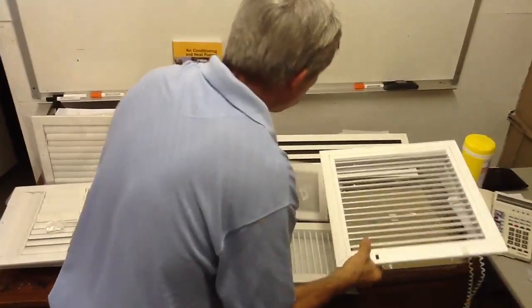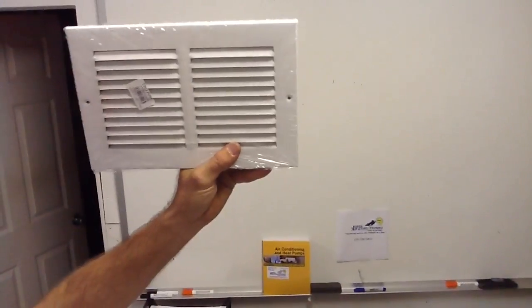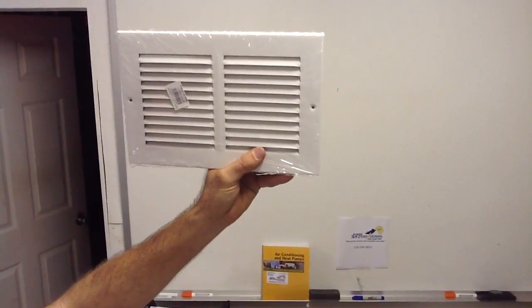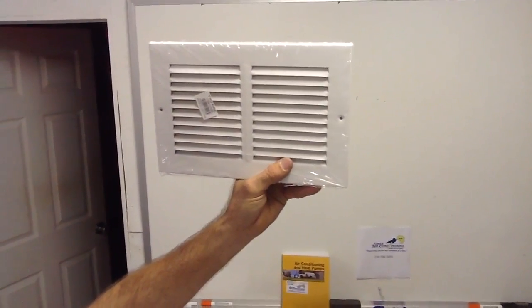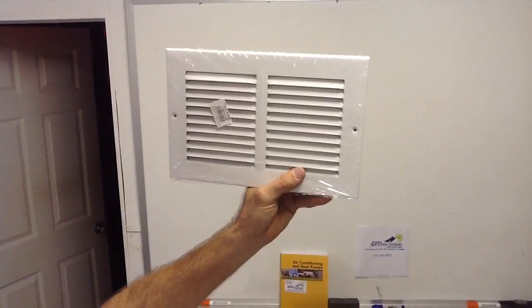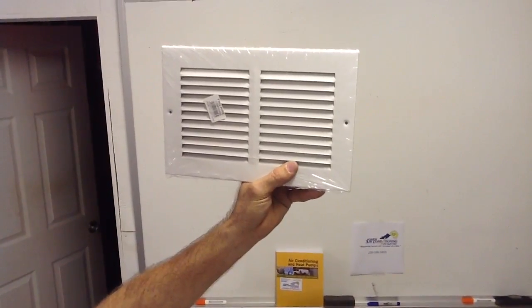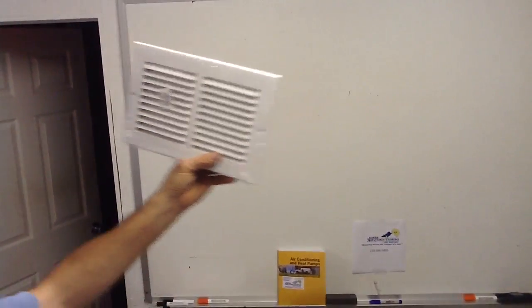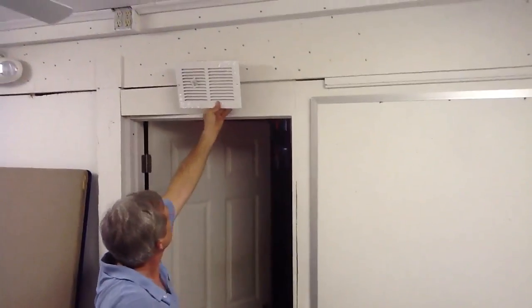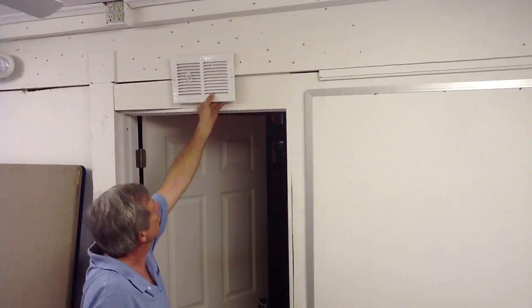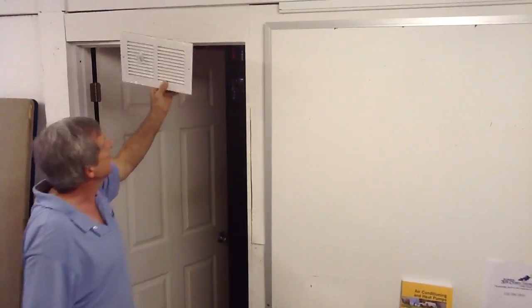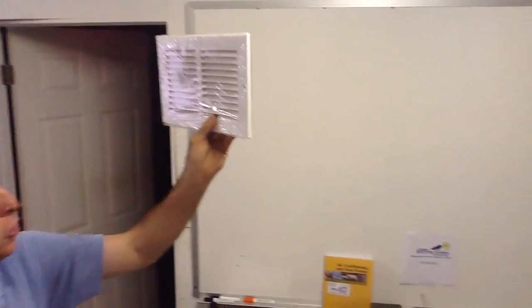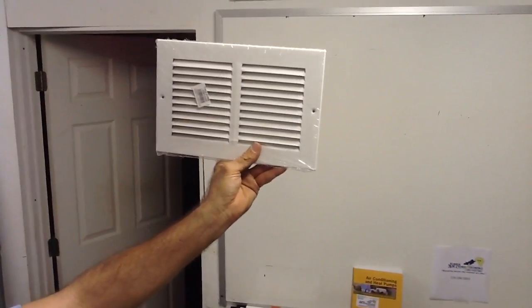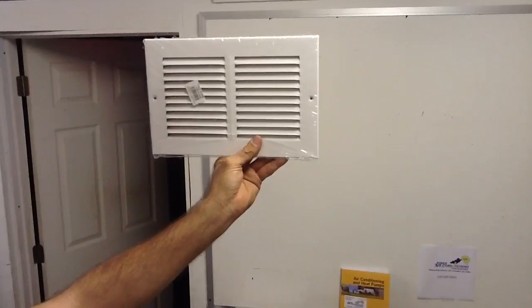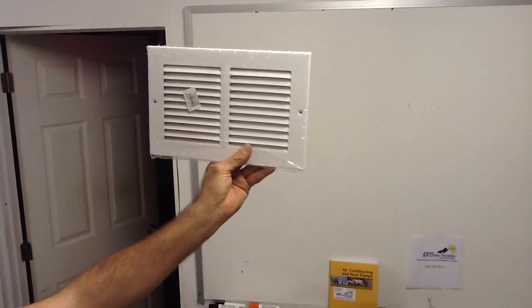This is what we call a pass-thru grill. This pass-thru grill, when you do a new job, you have to put returns in every room. So the easiest way to do this a lot of times, because of the ceiling height or because of the location of the room, you put pass-thrus over top of the door. You just cut a small hole, you screw one on this side, one on that side, and the air is allowed to pass through because you're supplying air in the room with a positive pressure. And actually what this does, it helps equalize the pressure in the room.